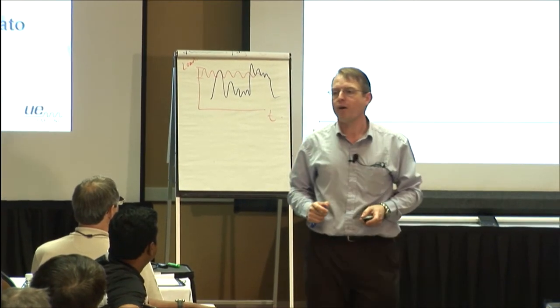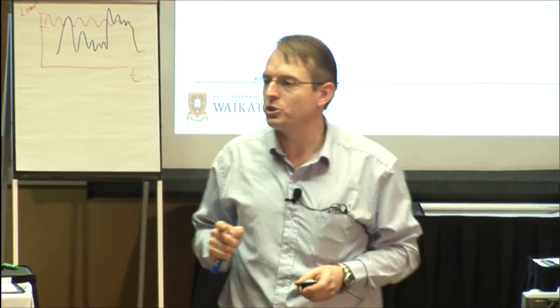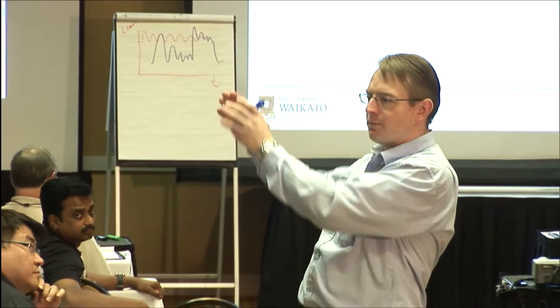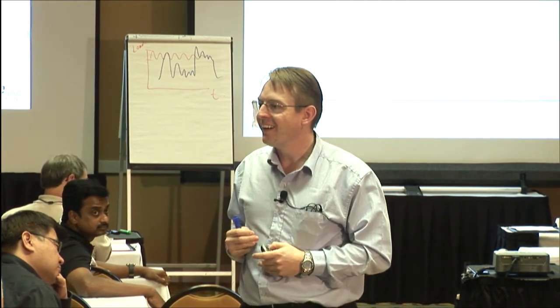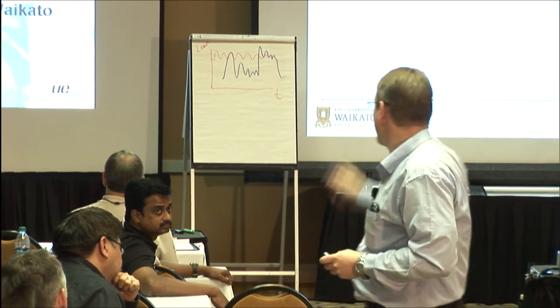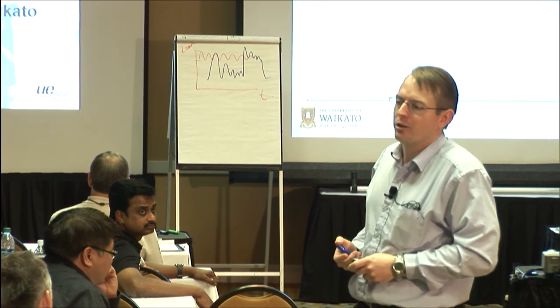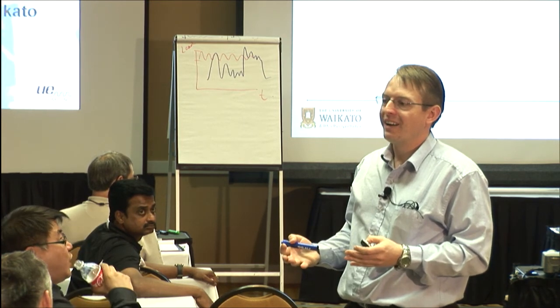But I will say this: my pet hate on this sort of work being done. A lot of people come in, as I call them, the super slick salesmen. They might put a little logger box on, log a few amps, and then, hey presto, that lines up with this shiny gray box or blue box or green box or pink box, depending on which company they represent. This is our magic option, and I'll save you 35%, is the classic marketing phrase. It all depends on what your true profile is, and the only way you're going to get that is if you actually measure it. And when I say measure it, I'm not talking about measuring amps at the compressor, I'm talking about measuring flow, measuring pressure, and understanding where you're at.